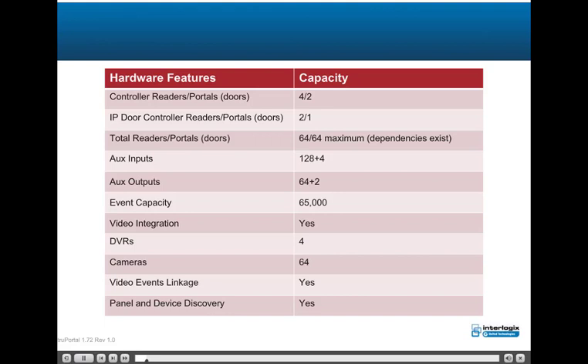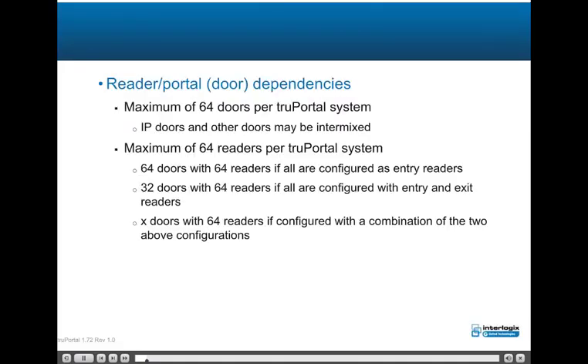Panel and device discovery is available within the application. truPortal supports a maximum of 64 doors per system. The doors can be a mix of controller-based doors, IP-based doors, and other door controllers. 64 doors with 64 readers if all are configured as entry readers; 32 doors with 64 readers if all doors are configured with entry and exit readers; or a variable amount of doors with 64 readers if configured with a combination of the two configurations.